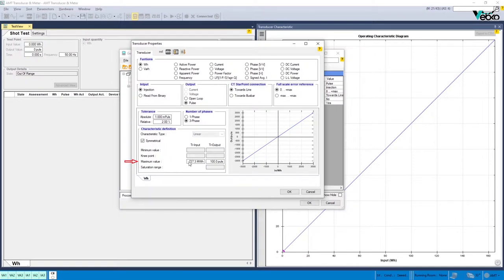is possible to enter the amount of power and the number of pulses received in exchange for that amount of power. Usually, the meter factor, or C/R, is entered in this section. For example, the factor for an EDMI MK6E meter equals 5000 watt-hour per pulse.